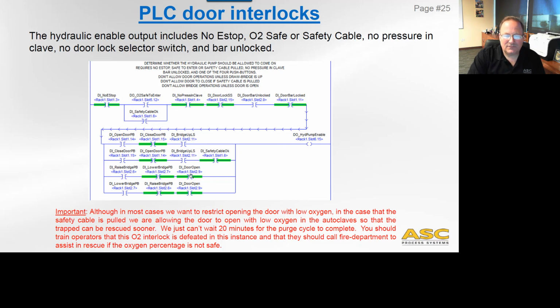Okay. Now the other thing that we changed in this logic is when we try to open the door, we're going to require that the bridge is up before the hydraulic pump kicks on. And when we try to close the door, we can't close the door if the safety cable is not okay. And so this specific thing says, although we are safe over here, and we might allow the safety cable to operate the hydraulic, we're not going to let it operate if the purpose is to close the door. We don't want to close the door on someone who has pulled the safety cable. And then on the bridge operations, we want to make sure that the door is open.